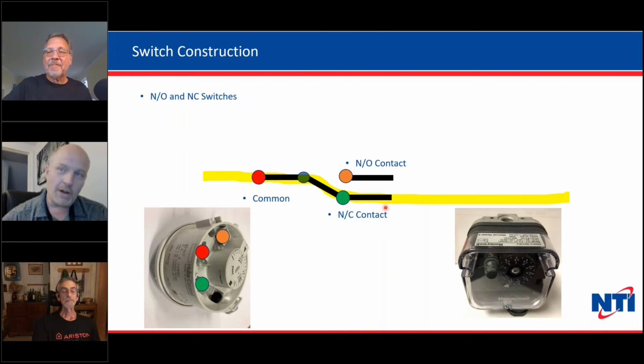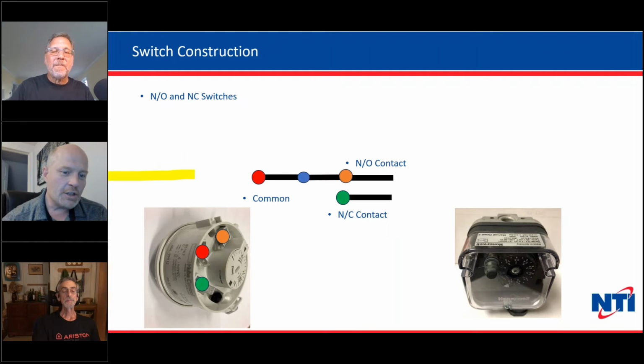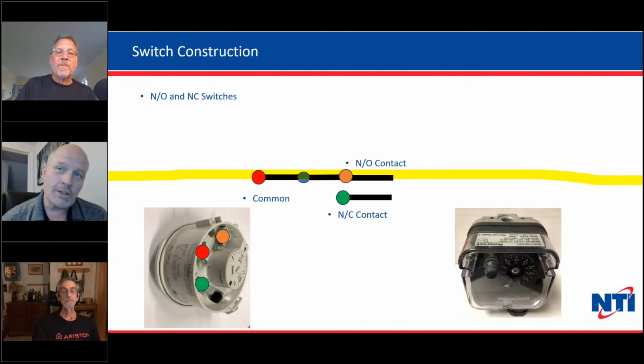So yeah, now if we trigger this switch, so let's do that. It kind of does what you might expect, which is you're going to open the normally closed contact and you're going to close the normally open contact. I guess in theory, you could take power away from something and apply it to something else, but typically these switches are not used in that fashion. Usually just one thing occurs.